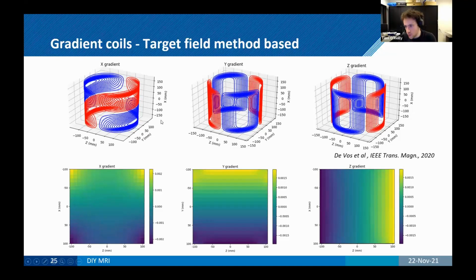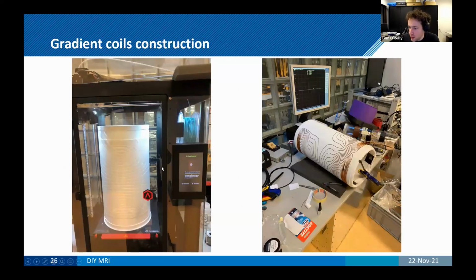Yeah, we have that as well, but then the Y and the Z gradients for us are very different in design. And these two are much more efficient by about a factor of 2 than the X gradient coil. So typically this will be your limiting factor, both in terms of efficiency and in nonlinearity, because you see quite strong gradient nonlinearities here. To build them, get a 3D printer. Actually, for everything with low field, 3D printers are your friends because it just makes everything so much easier that you can build it in-house.